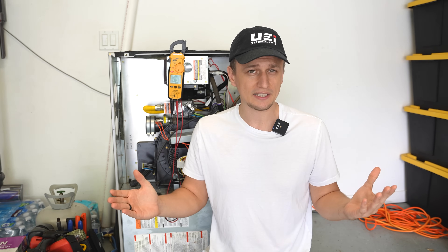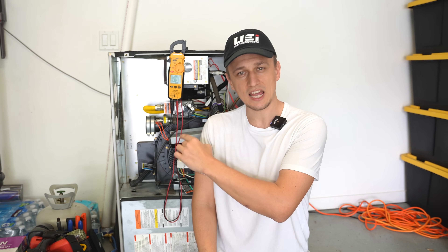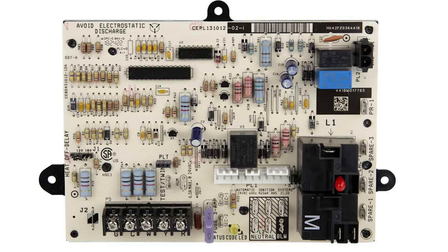If you're experiencing a problem similar to the one I just described, hopefully this video will be able to help you out. The original question: is it a bad gas valve? It could be, but most likely not. There are plenty of other things that can go wrong and cause the gas valve not to open. The first thing I would suggest checking before anything else is to see if the furnace control board is blinking any error codes.